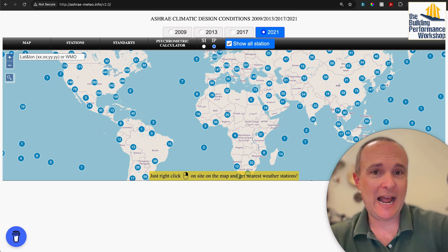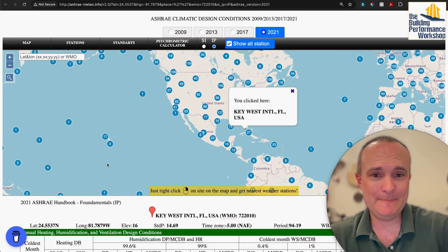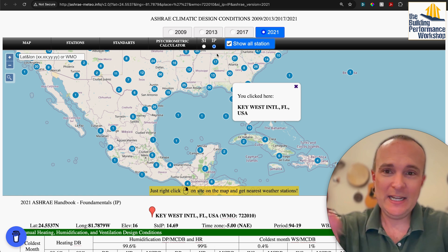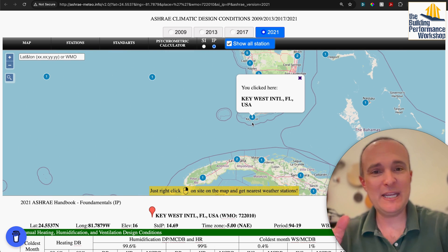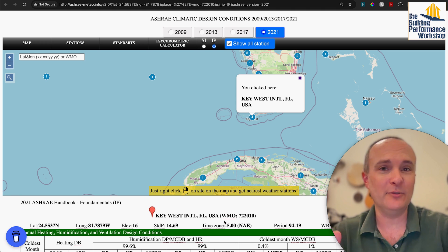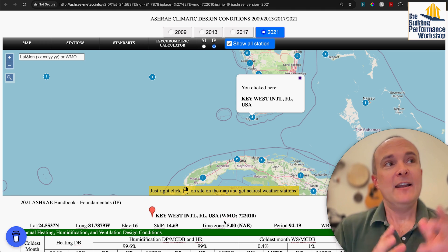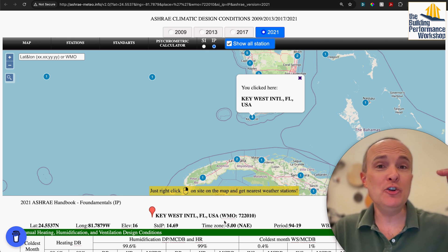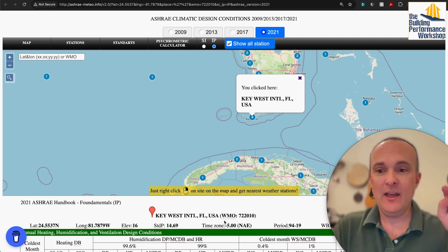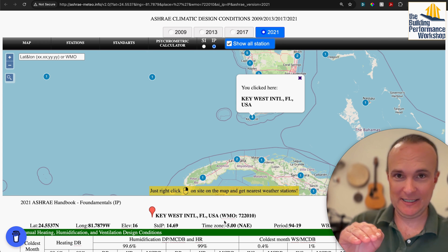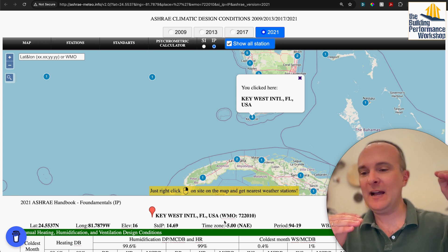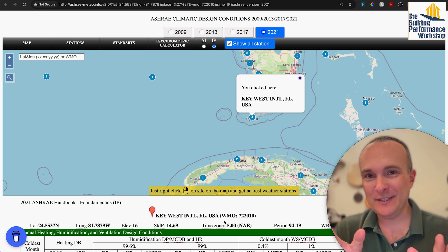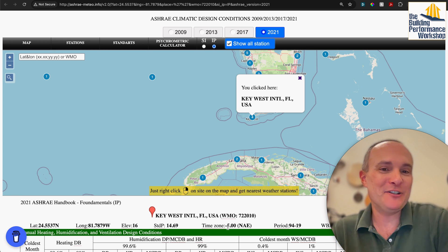As an example, we're going to start with a place I think of as kind of an extreme environment, which is Key West. In southern Florida, for most of the year, the temperature and humidity of the outside air makes the dew point of that air higher than the average temperature of indoor spaces. Which means if any outdoor air comes in contact with inside temperatures, it will make those surfaces wet — and that's a really dangerous thing. That's why Florida is particularly interesting for people who do what I do.